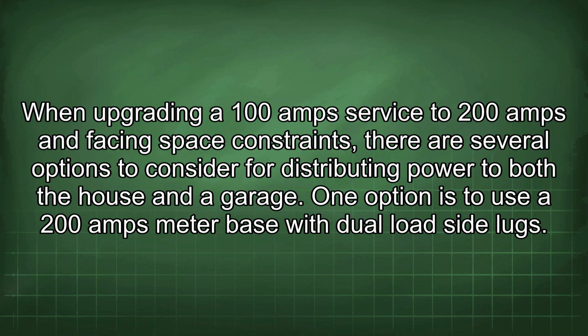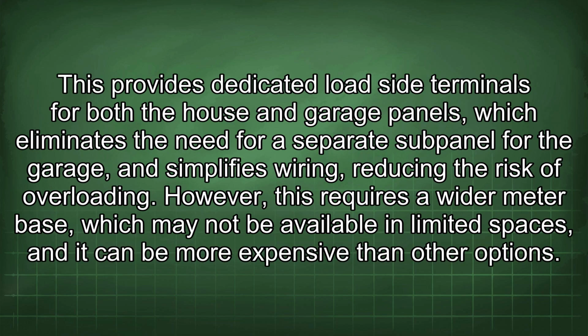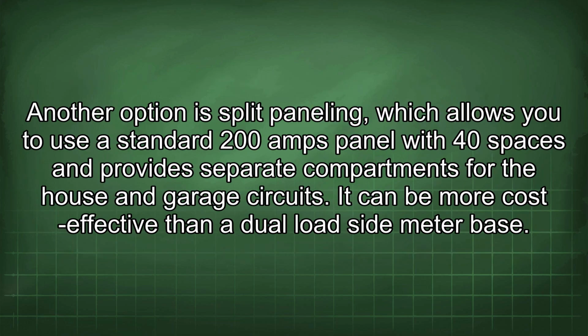One option is to use a 200 amp meter base with dual load side lugs. This provides dedicated load side terminals for both the house and garage panels, which eliminates the need for a separate subpanel for the garage and simplifies wiring, reducing the risk of overloading. However, this requires a wider meter base, which may not be available in limited spaces, and it can be more expensive than other options.